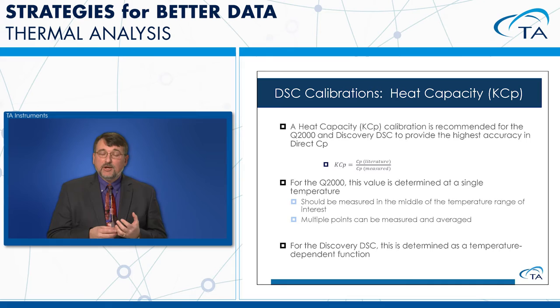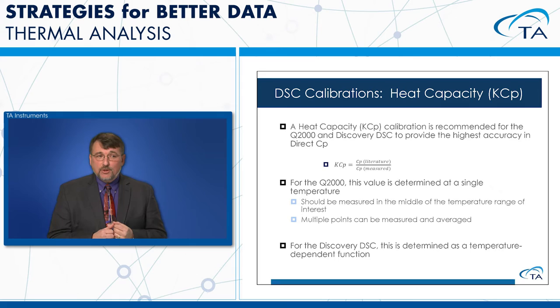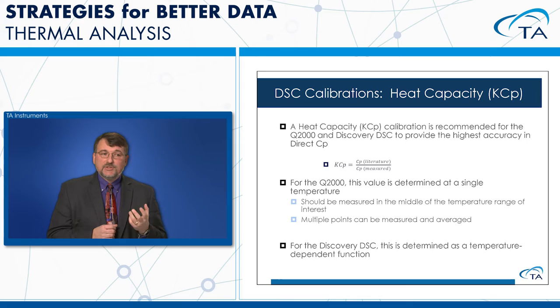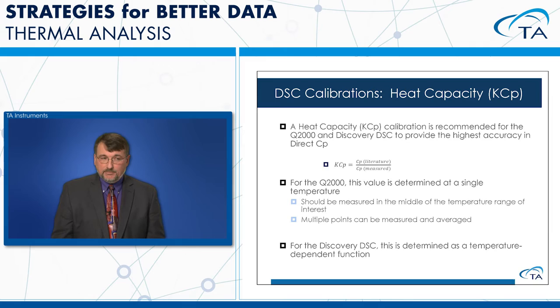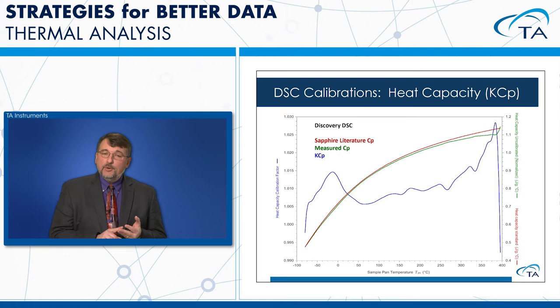The heat capacity calibration is used to get the direct value of heat capacity on a T0 DSC like the Q2000 or Discovery DSC. We take the literature value of heat capacity of a known material — typically sapphire — and compare it to what we measure. On the Q2000, we take a value at a single temperature and divide; on the Discovery DSC, we fit the whole curve as a temperature-dependent function for a better measurement. The measured curve for Discovery DSC matches the sapphire literature value very well.